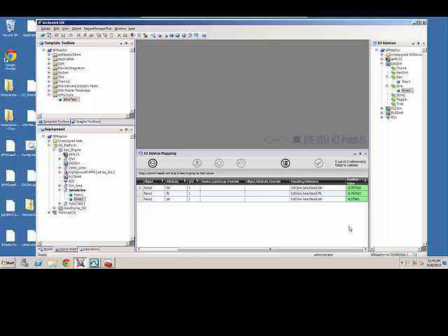You can see this data is going to be moving. It's going to refresh and give me a new value here. So that's basically what you do. You could type these addresses in by hand if you want, but I'm using the auto assignment. The interesting thing about this is the actual name that I renamed it with, fsine1. That means it's going to return a floating point. If I named it with a B, it's going to return a binary number. So the actual first letter of the tag has to do with what type of value it's going to return, F being the floating point.